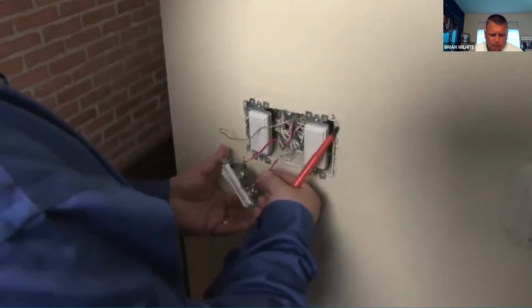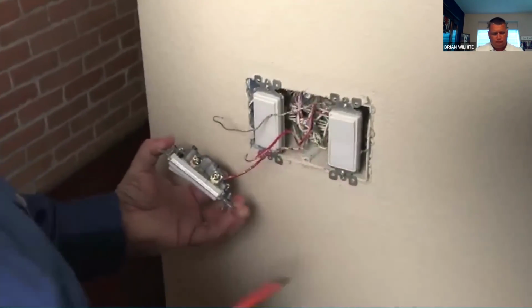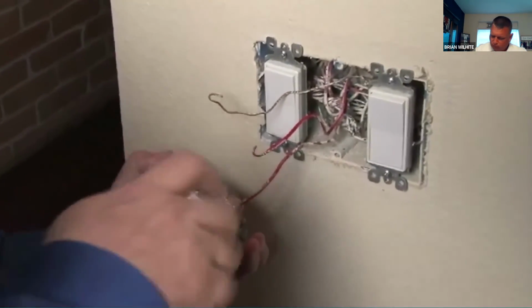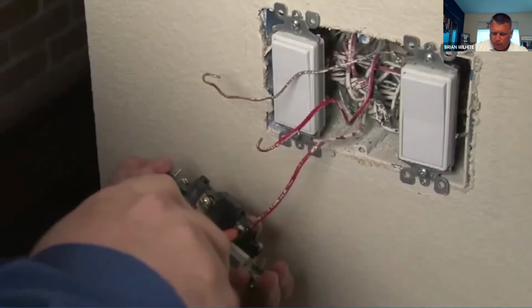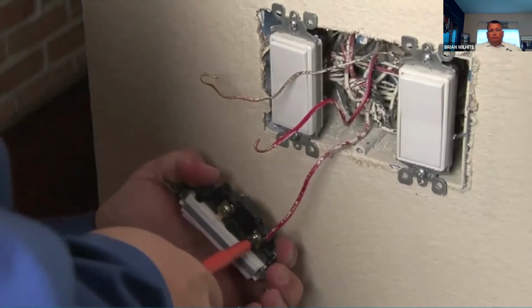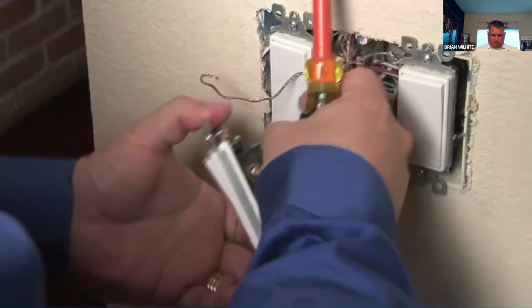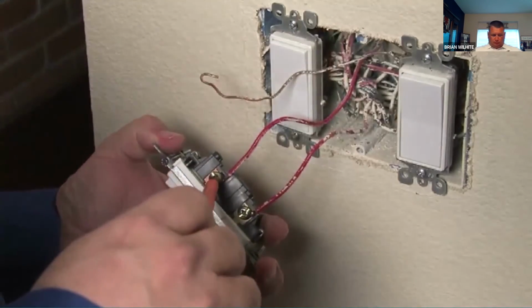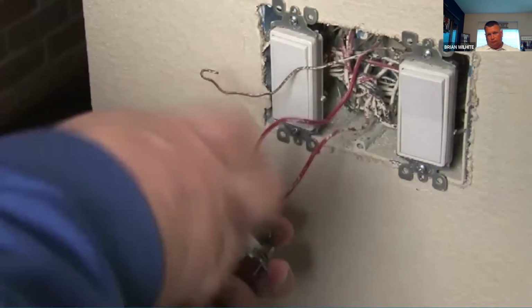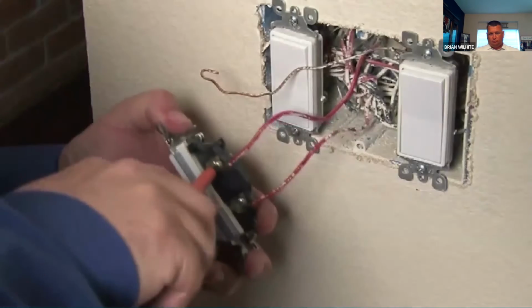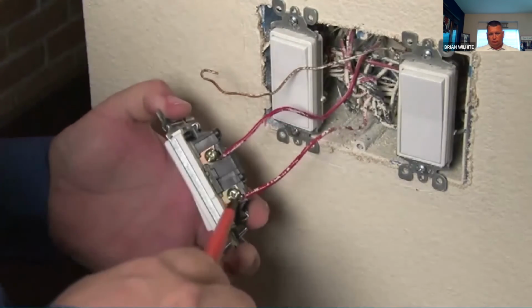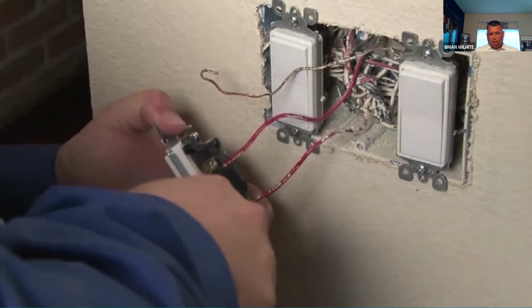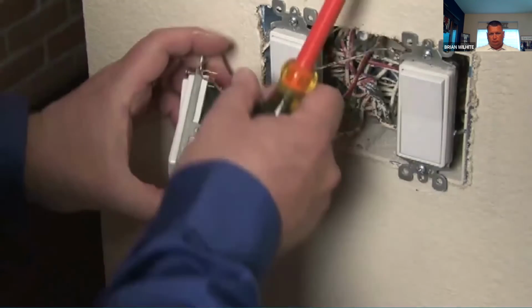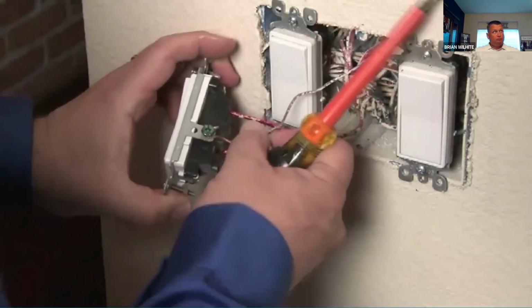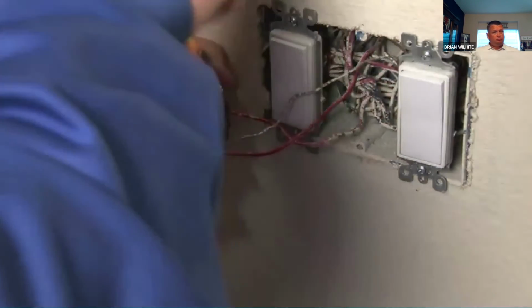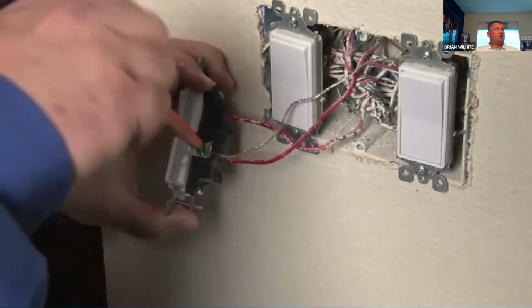Okay, technician is now going to install the new light switch. He's going ahead and connecting one wire to the one set screw, making sure that the screw is tight. And then the second wire to the set screw. Also make sure you torque down, make sure it's good and tight. Also make sure the loop is going in the direction that the set screw turns. That way it's tight and the screw doesn't unwind. Now he's doing the ground. Follow the same steps. Make sure it's good and tight.